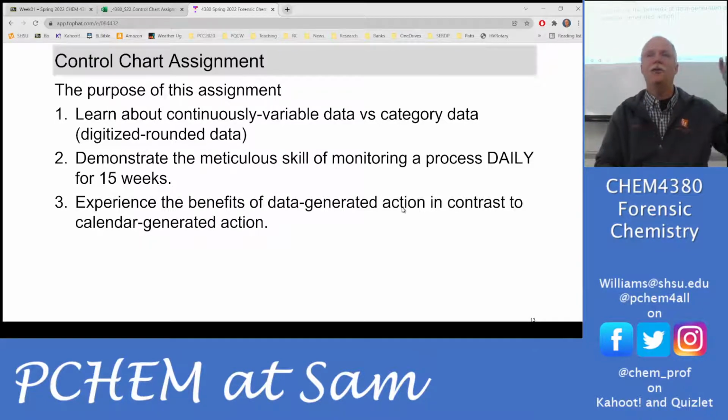Then Monday, you calibrate the instrument and you realize it's been out of control. You don't know when it went out of control. So you have to throw out all of the previous week's data back to Monday, because that's the last time it was in control. So you've put a question mark on that data, and you have to throw it out and redo it. So that's a problem of just not tracking that process daily.